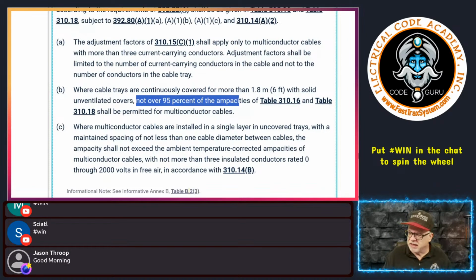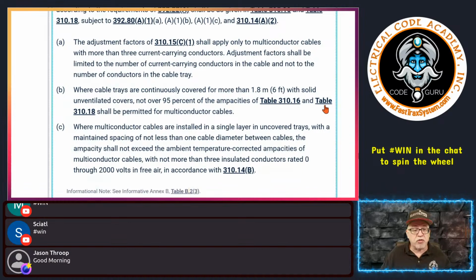Okay, now that's also going to be applicable to both, whether 310.16 is in play or those conductors that are being used in that cable are 150 degrees, for example, not 90 but 150. Then you would be using table 310.18. Either way, you're going to be limited, okay, to 95% of that ampacity.